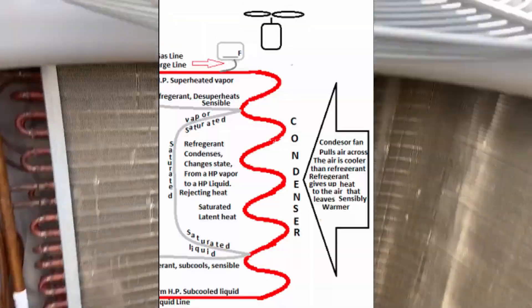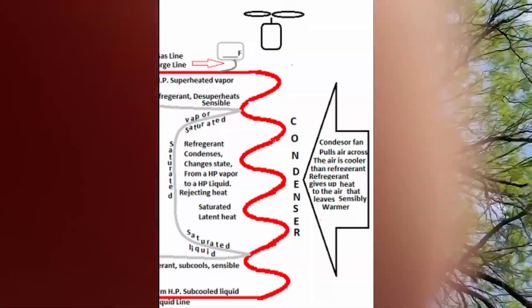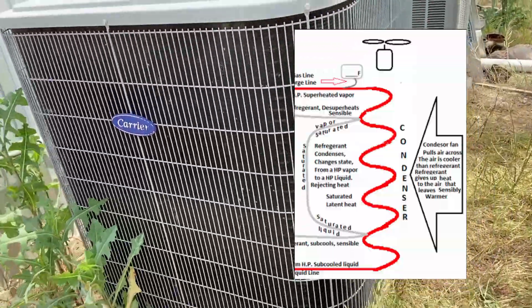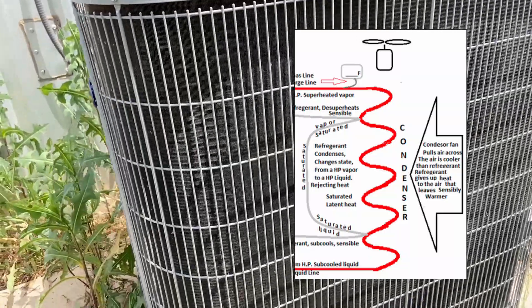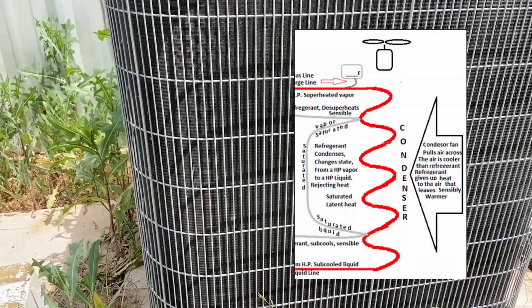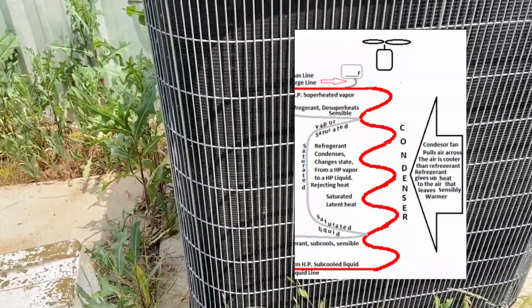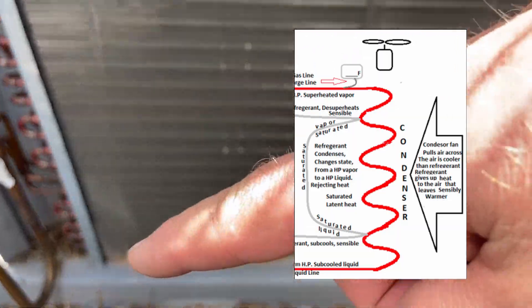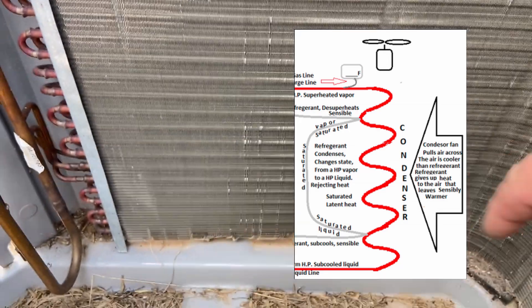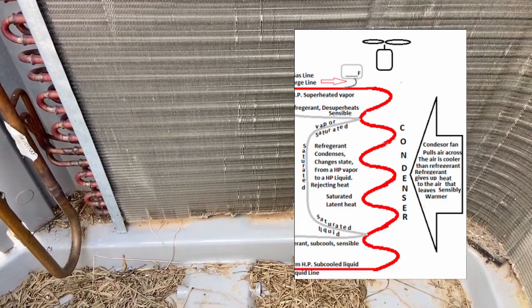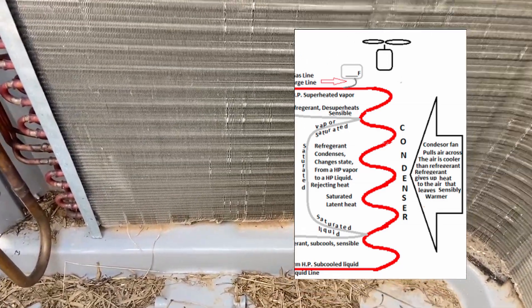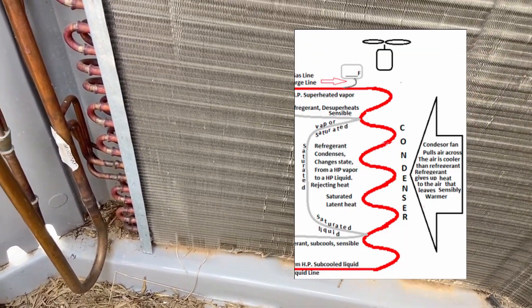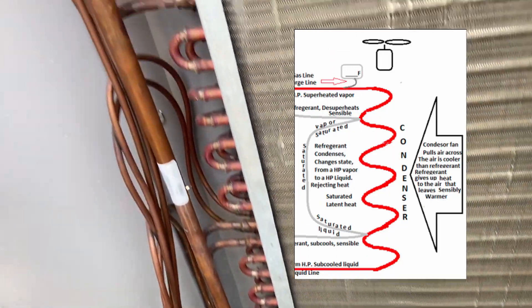If we look on the outside, we can see the same thing — it's just simple heat transfer: refrigerant changes from a vapor to a liquid, rejecting heat. The majority of this is going to be at saturation. Now, after we've changed state from a vapor to a liquid, the very bottom part of this condensing coil is subcooling — it takes the refrigerant below saturation, which we call sensible heat.